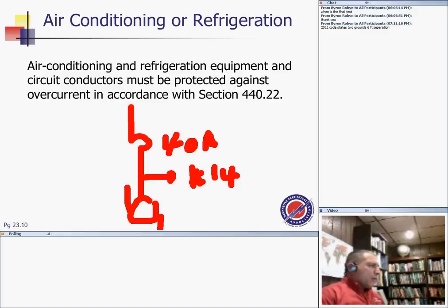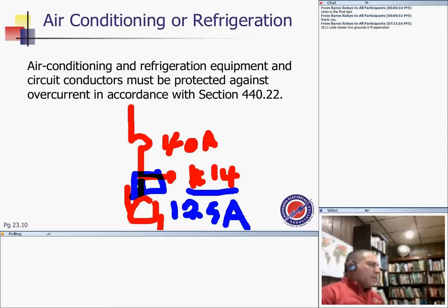Now, most motors have a controller here, and inside the controller is an overload protection. So the overload protection here will protect the conductor. The motor itself will not take more than, because it's continuous, more than actually 12.5 amps. With the motor, it will not take more than 12.5 amps, number 14 is good. And who regulates this? The overload. So that's a special condition for motors.